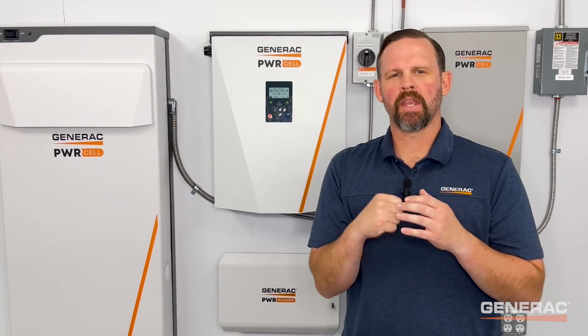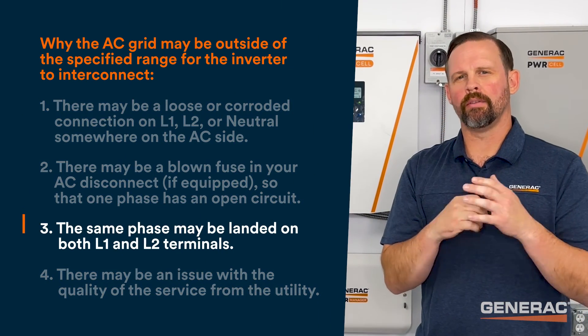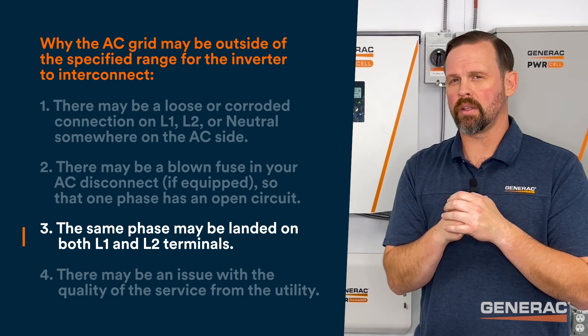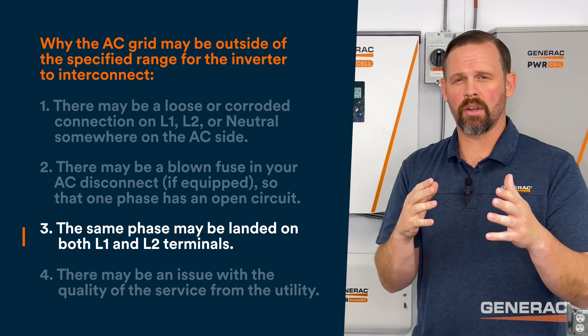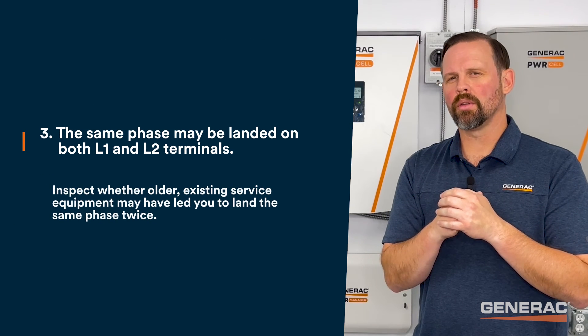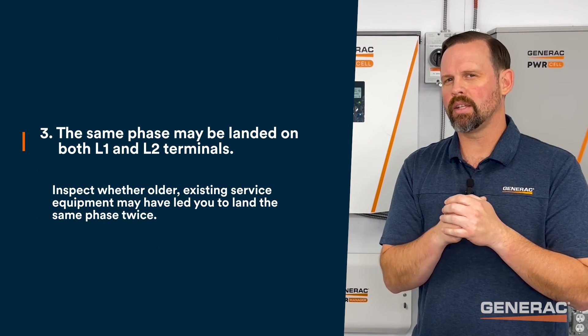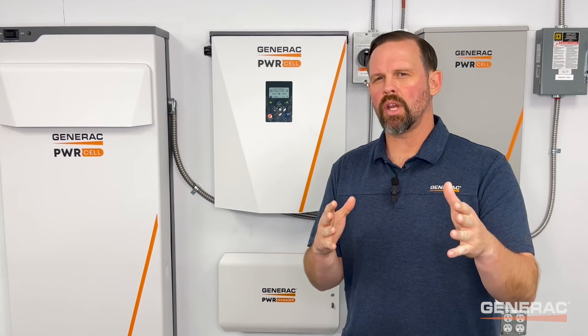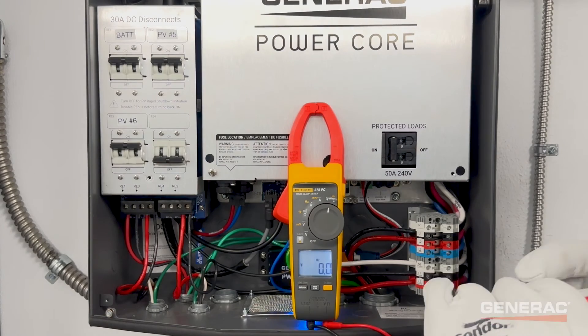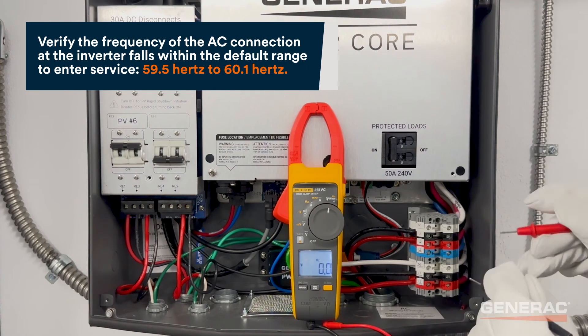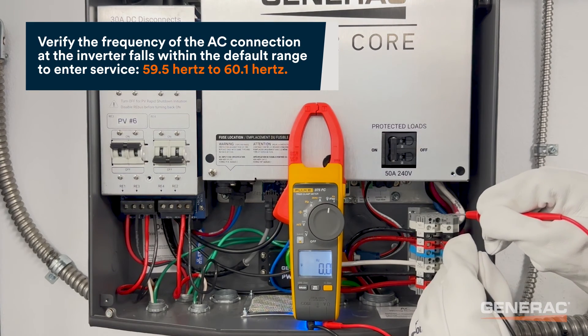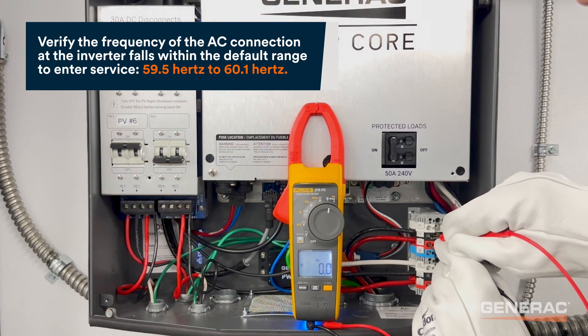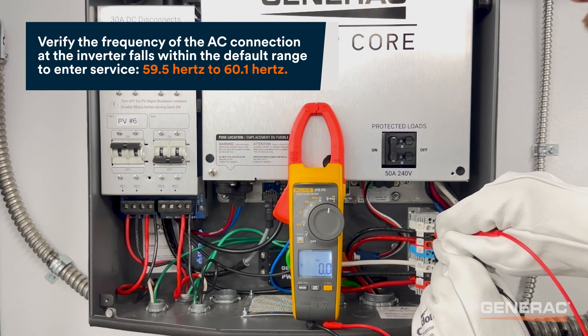Reason number three: if you don't measure nominal voltage of 240 volts line to line at the AC grid connection terminals of the inverter, and instead you measure zero volts, inspect whether older existing service equipment may have led you to land the same phase twice. If AC voltage measurements check out, change your selector to measure frequency. Verify the frequency of the AC connection at the inverter falls within the default range to enter service, 59.5Hz to 60.1Hz.